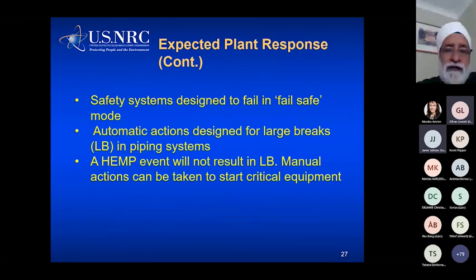We also know that safety systems are designed to fail safe. In other words, if you lose power, the device will fail into a safe mode. Automatic actions that we need are critical for large breaks in the nuclear power system. We do not expect any line breaks. We do not expect any accident conditions just because an EMP event occurred. We have time to take manual actions.